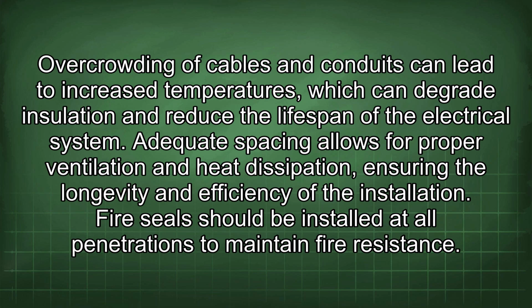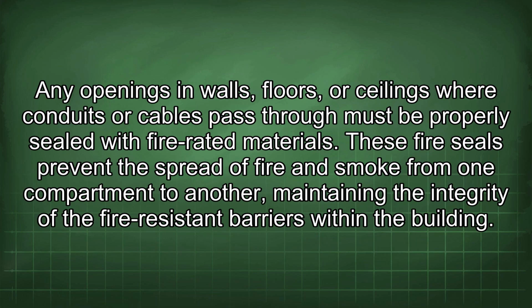Fire seals should be installed at all penetrations to maintain fire resistance. Openings in walls, floors, or ceilings where conduits or cables pass through must be properly sealed with fire-rated materials. These fire seals prevent the spread of fire and smoke from one compartment to another, maintaining the integrity of the fire-resistant barriers within the building.